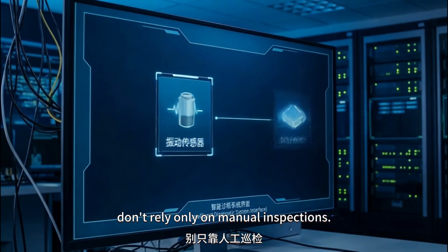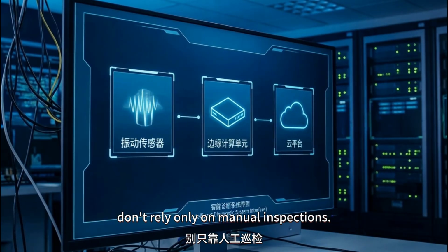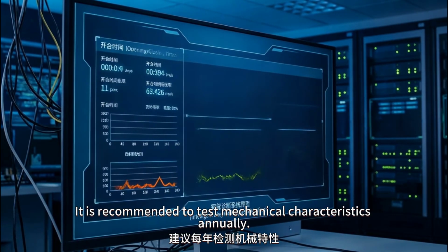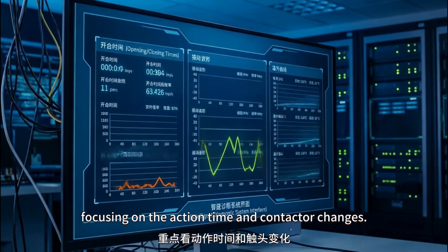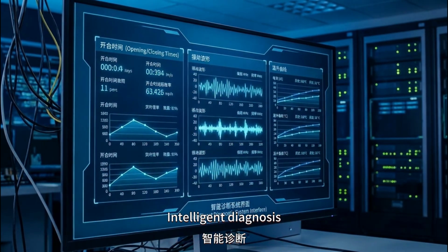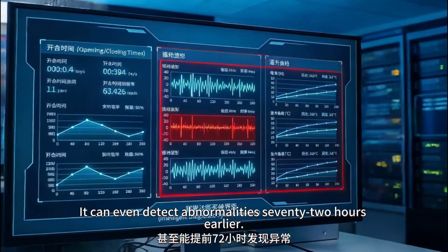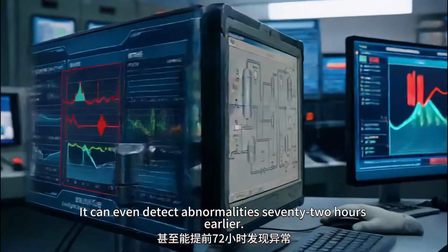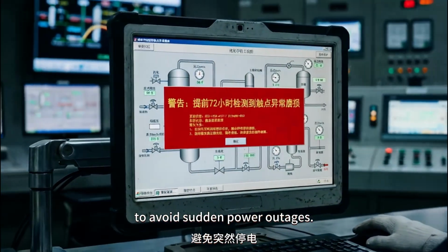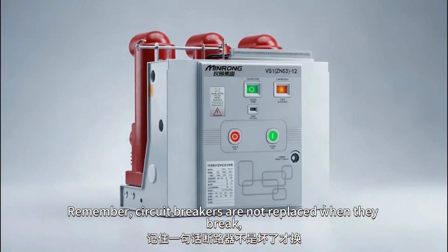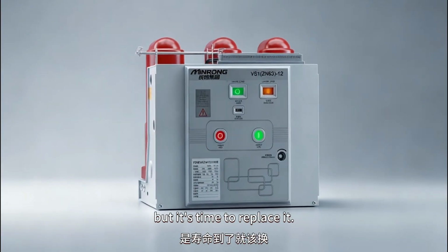In operation, don't rely only on manual inspections. It is recommended to test mechanical characteristics annually, focusing on the action time and contact changes. Intelligent diagnosis can even detect abnormalities 72 hours earlier to avoid sudden power outages. Remember, circuit breakers are not replaced when they break; it's time to replace them before that.